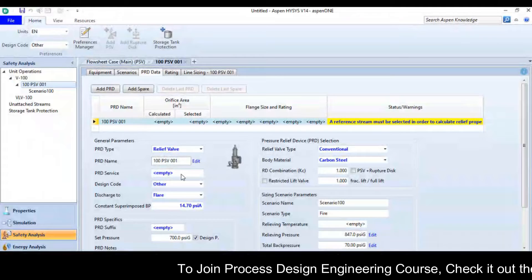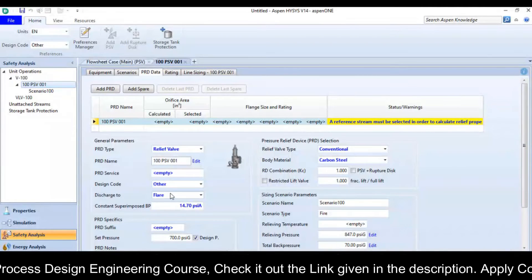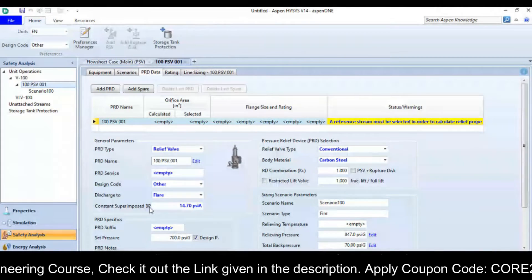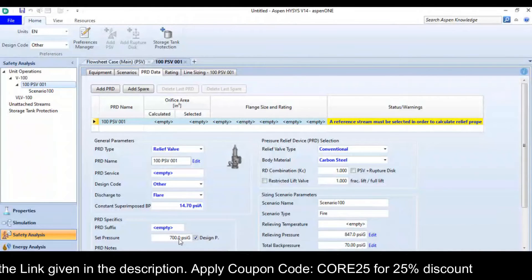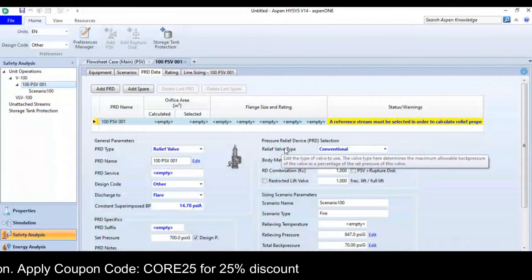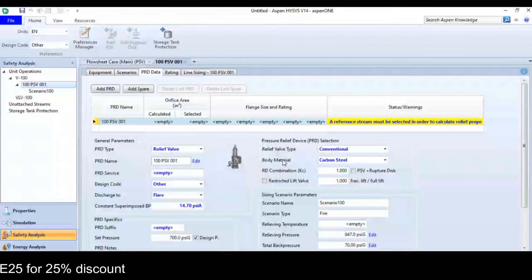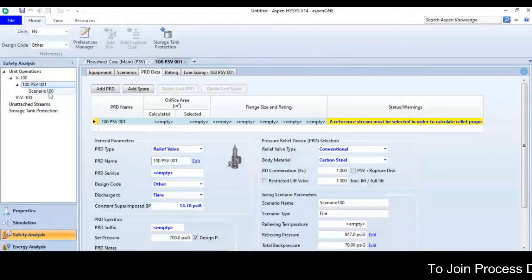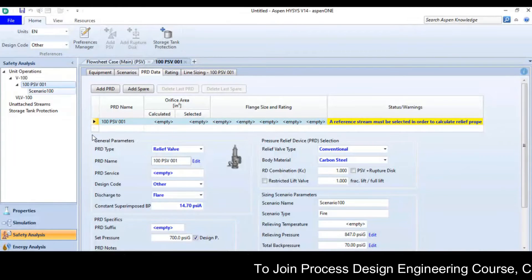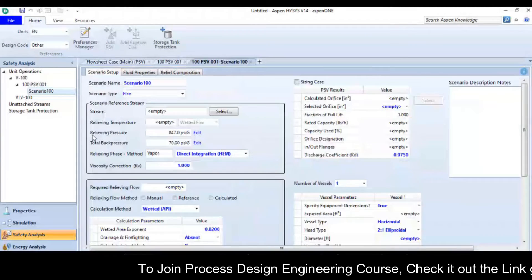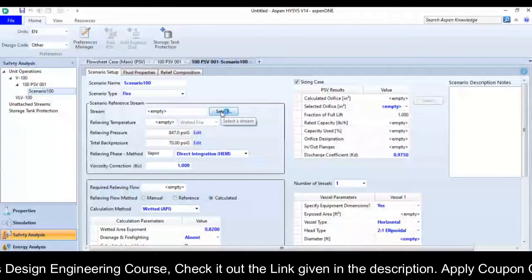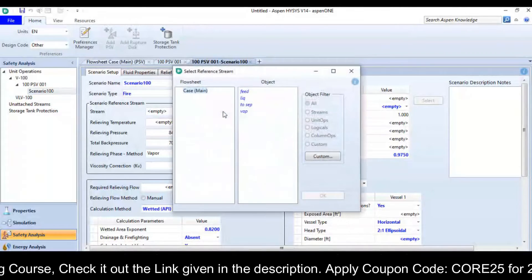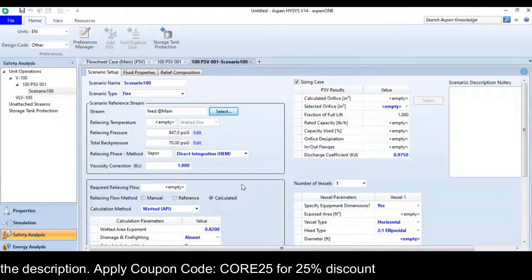After selecting a fire case, I will go to PRD data and define the relief valve specification. Here it is a relief valve, the design code is other for the API, the discharge location is flare, the constant superimposed back pressure, the set pressure is also there, the relief valve type is conventional and the body material is carbon steel.